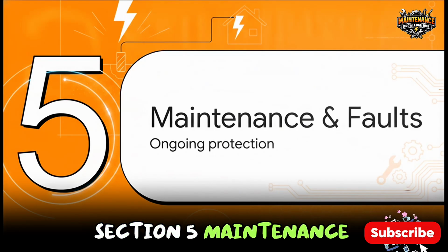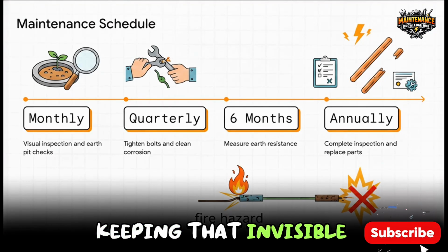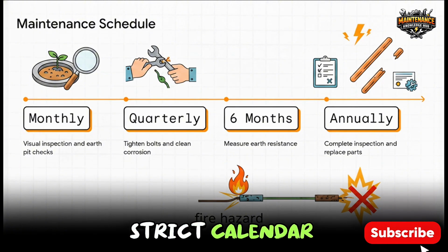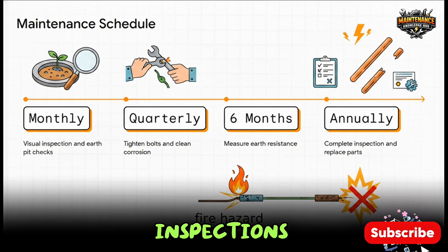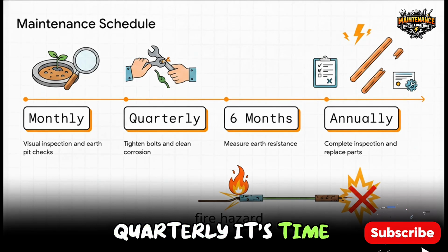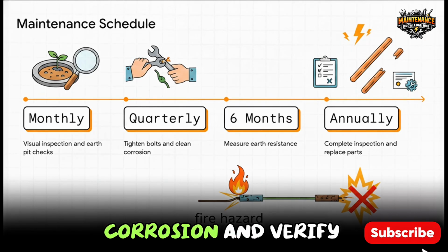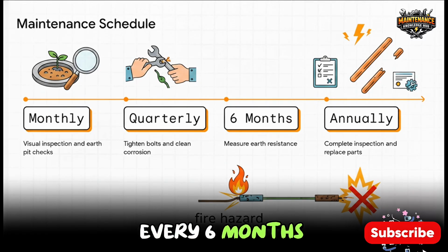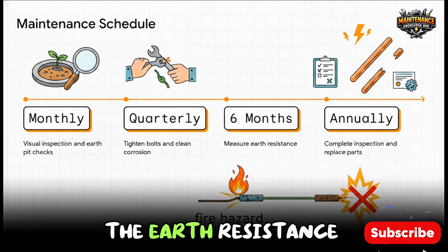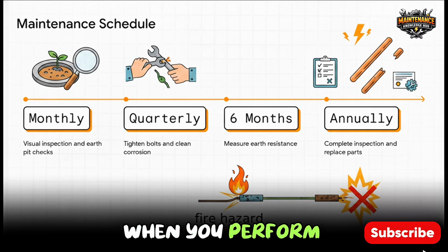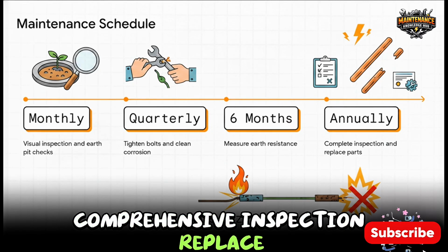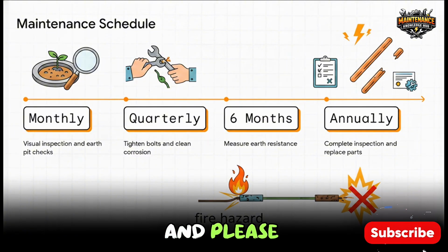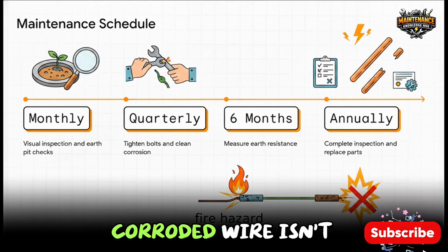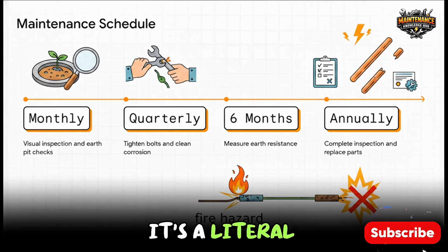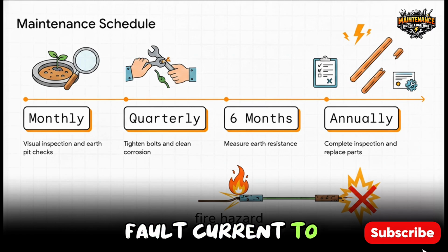Section 5. Maintenance and common faults. Keeping that invisible shield intact requires a pretty strict calendar. Monthly, you should be doing visual inspections and checking out those earth pits. Quarterly, it's time to physically tighten the bolts, clean off any corrosion, and verify your bonding. Every 6 months, you got to pull out the testers and actually measure the earth resistance. And annually, that's when you perform a complete, comprehensive inspection, replace any damaged components, update your records, and please make sure your test instruments are actually calibrated. Because a loose bolt or a dry, corroded wire isn't just an annoyance, it's a literal fire hazard waiting for a fault current to find it.